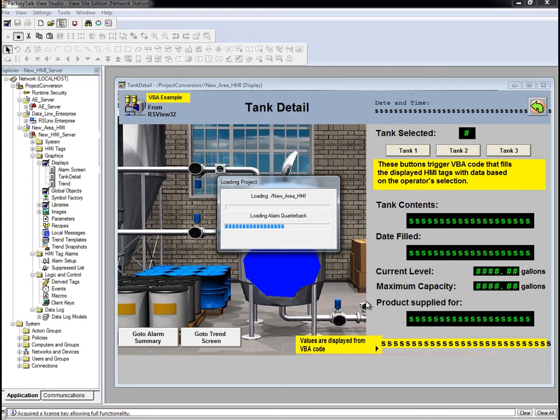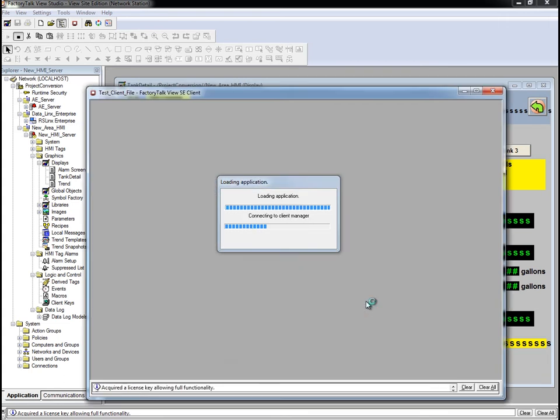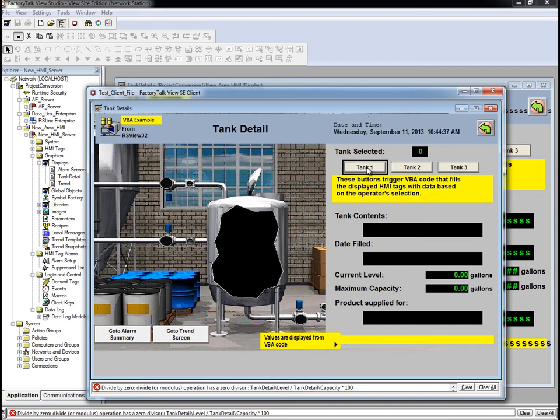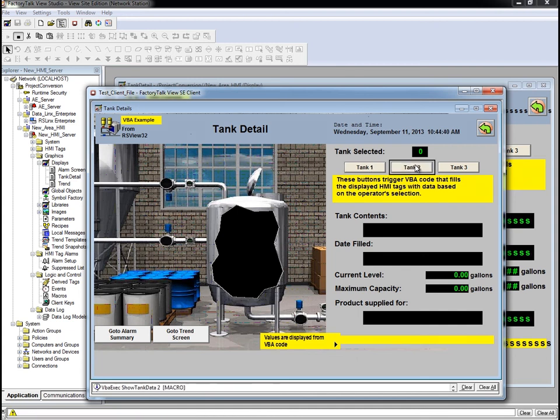When the client starts, you can see that communications are working and talking with the controller. The same application is running that was running in the RSView32 environment. Since the initial RSView32 screen got most of its data from the controller using VBA, notice that we do not see tank values updating as we click the tank buttons.